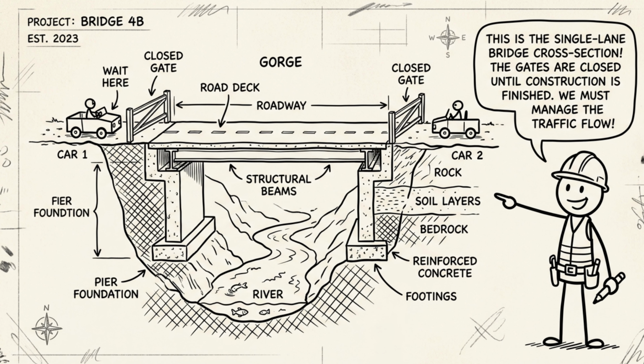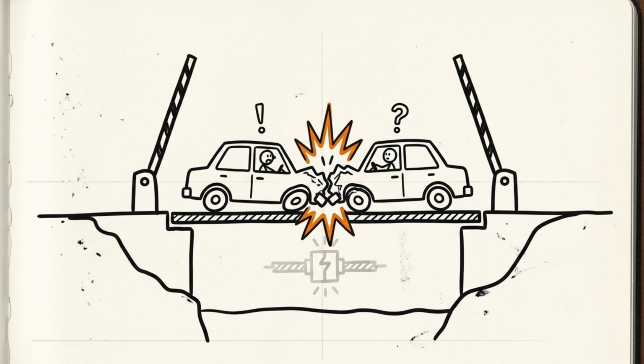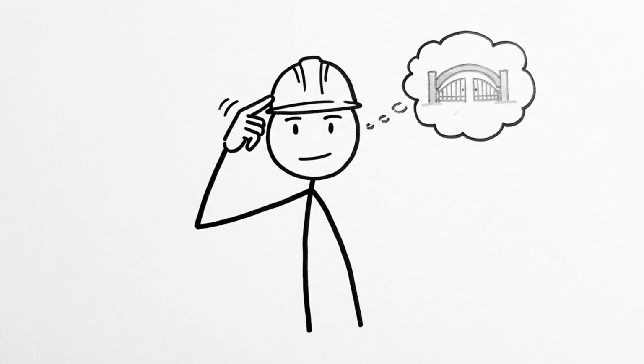Picture a single-lane bridge with a gate on each end. Cars can cross toward town or cars can cross away from town, but the gates are built so both directions can never be open at once. Open both gates together, and cars from opposite directions meet in the middle at full speed. That's exactly what happens electrically if a transfer switch fails or is bypassed, while the grid comes back online mid-outage. 2 unsynchronized power sources collide on the same wire. Hold on to that single-lane bridge picture. It's the reason every rule in the next 2 sections exists.